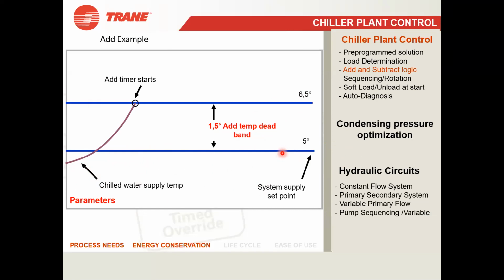So suppose one chiller is running, and the associated pumps and other accessories are also running, but now your load has increased. The office has got more people, so the load has increased. So what will happen? It will not be able to maintain the 5 degrees centigrade temperature. It will start increasing slowly, and once it reaches the dead band, your timer will start.